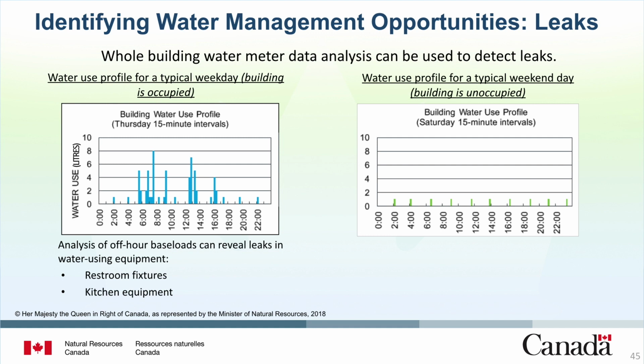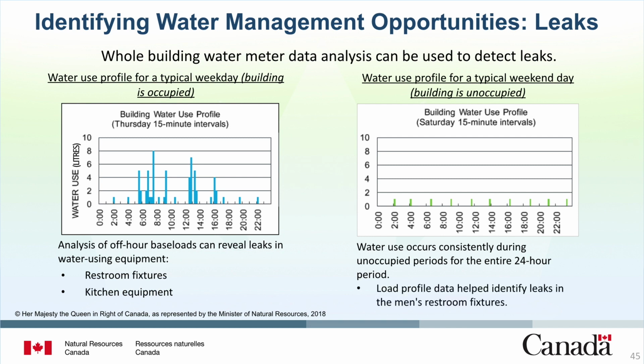Water use trends can also be used to identify efficiency improvements needed by water-intensive systems. This water use profile illustrates possible plumbing fixture leaks using data from a building-level interval pulse-type water meter profile for a 24-hour period. The figure on the left is the water use profile for a typical weekday. The figure on the right is the water use profile for the same building on a weekend day when the building was unoccupied. As you can see, water use occurs consistently during the unoccupied period over the entire 24-hour period. Using the load profile data, the building operator can identify leaks in the men's restroom fixtures.